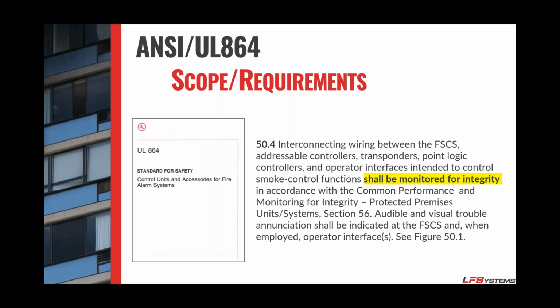However, with smoke control and with life safety devices, we have to verify that what we are being told is what they want to happen. What I mean by that is if you want it to run, you have to close a run contact and open a stop contact. If you want it to stop, you have to open the run contact and close the stop contact. It's verifying not just through a single point, but through a dual point, that we are doing what we are told, because that's what they want. And most controllers on the market that are used for general pressure control use a single contact, whereas UL standards require a dual contact.